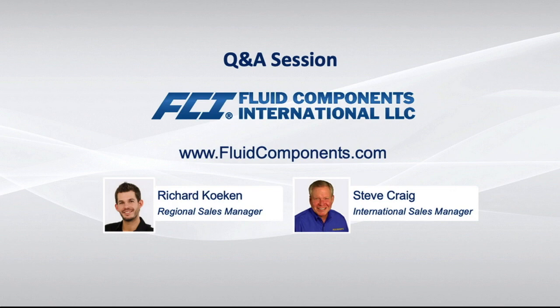What are the temperature limitations? Thanks, Katie. The maximum temperature for the flow element in the process is 850 degrees Fahrenheit, which is 454 degrees centigrade. And it does have a minimum of minus 50 F and minus 45 C. Which covers pretty much every application.